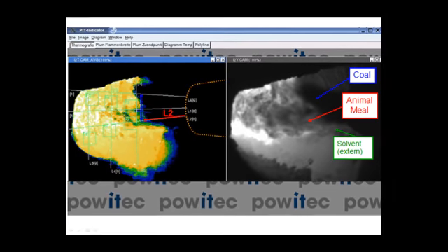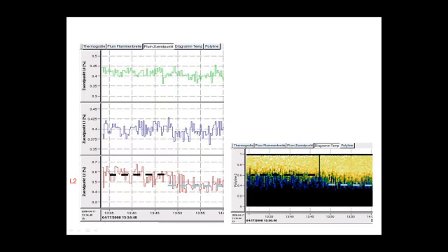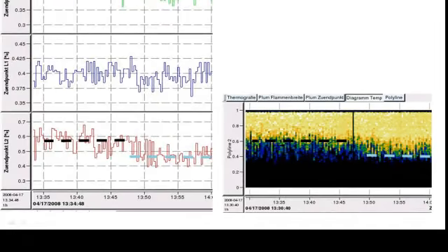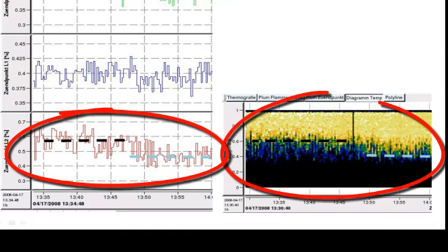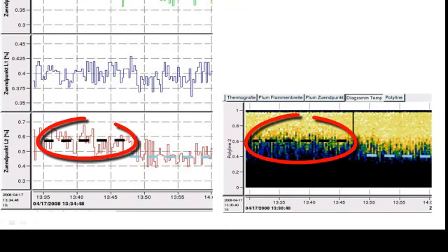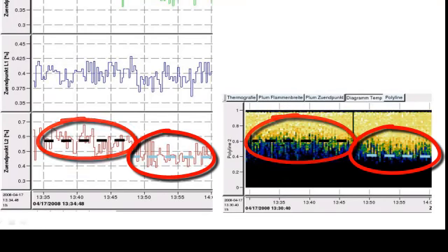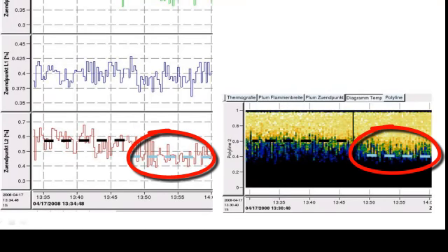Let's now focus on the polyline showing the ignition behavior of animal meal. Changes in the ignition are clearly represented as the ignition point signal value. This is what we call the plume function. There is a clear reflection in the polyline. If you look at the left-hand side, the ignition point in the first half of the picture was far away from the burner and in the second half went nearer to the burner. This is clearly reflected in the polylines.